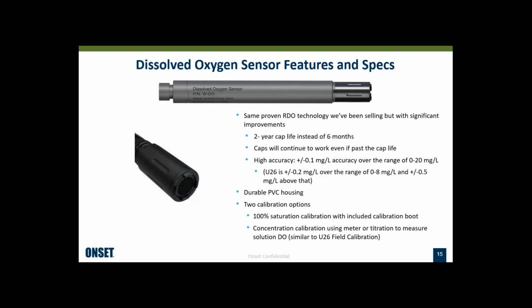There are 2 calibration options for the dissolved oxygen sensor. One is a 100% calibration using the calibration boot that we're going to include with every sensor. That's very similar to the boot calibration that users can do today with our U26 loggers. They can also do what's called a concentration calibration, where they put the sensor into a bucket with a known concentration of dissolved oxygen. They could use a bucket of salt water from their site, for example, use a meter to measure the dissolved oxygen content, and enter that in as their calibration reference point. So a couple of options.